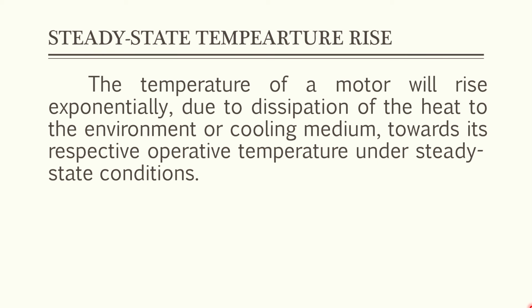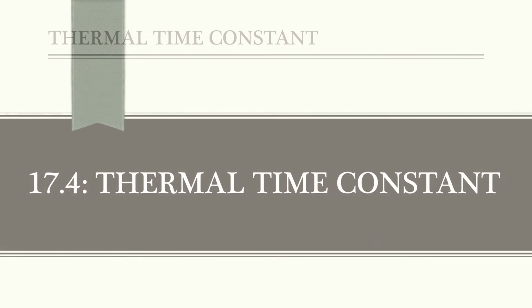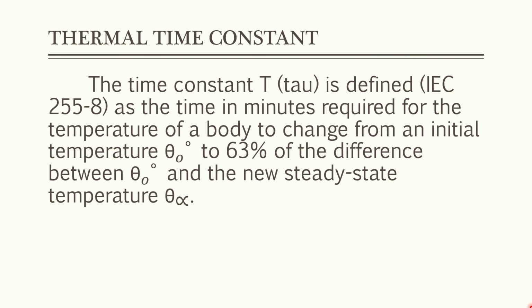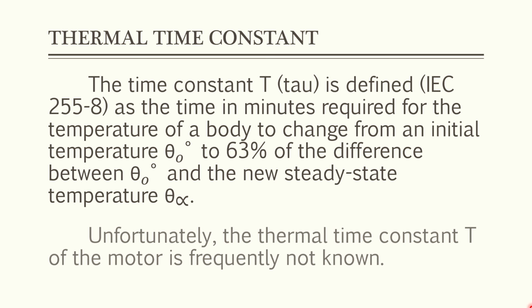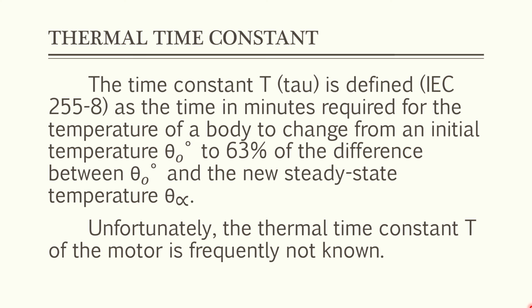The temperature of a motor will rise exponentially, due to dissipation of the heat to the environment or cooling medium, towards its respective operative temperature under steady state conditions. Thermal time constant. The time constant tau is defined in IEC 255-8 as the time in minutes required for the temperature of a body to change from an initial temperature to 63% of the difference between initial temperature and the new steady state temperature. Unfortunately, the thermal time constant tau of the motor is frequently not known.